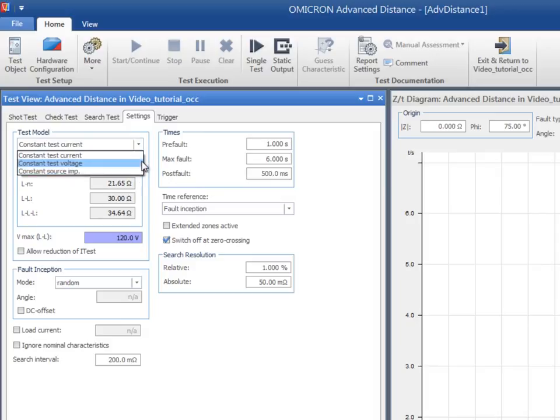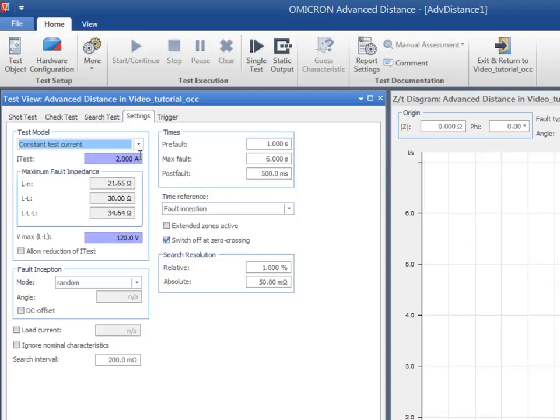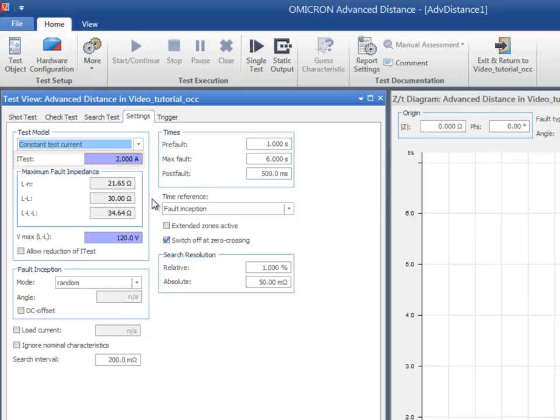Constant Test Current should be selected when testing Distance Protection relays with a current pickup setting. This way, the test current is set to the specified value and the relay voltage is calculated using the defined fault impedance of the test point. The pickup value for the relay under test is 1.8 amps, therefore 2 amps is suitable in this case.